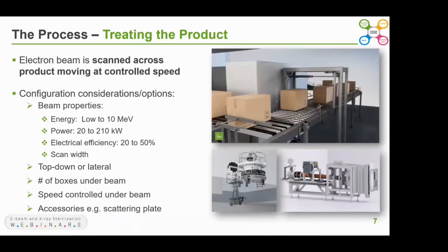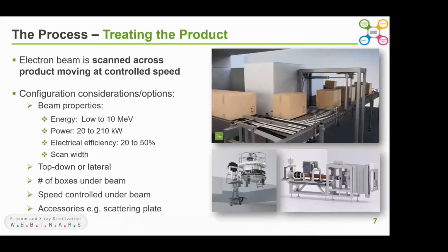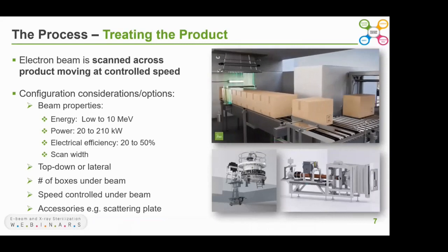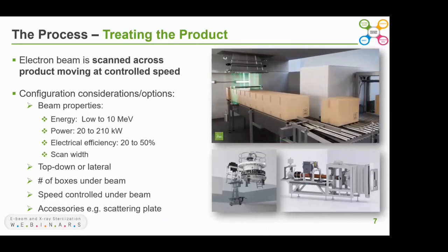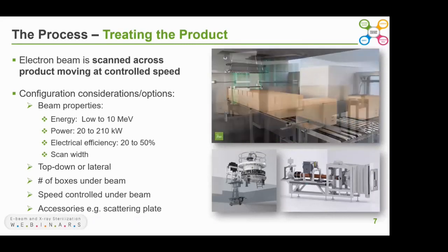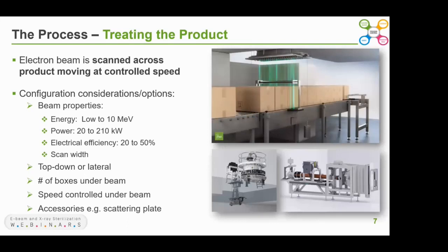Source selection requires determining a number of important properties, including the electron energy itself. This energy can range from hundreds of kilo electron volts to 10 mega electron volts. Energy selection is guided by product properties and the required dose uniformity ratio.